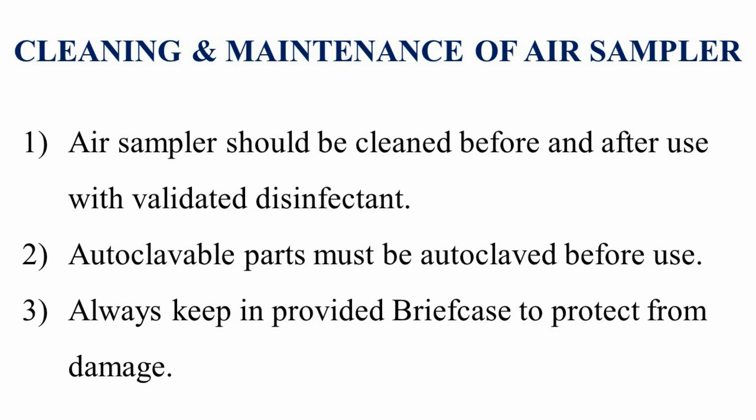Cleaning and maintenance of the air sampler. The air sampler should be cleaned before and after use with a validated disinfectant. Autoclavable parts must be autoclaved before use. Always keep the sampler in the provided briefcase to protect it from damage.